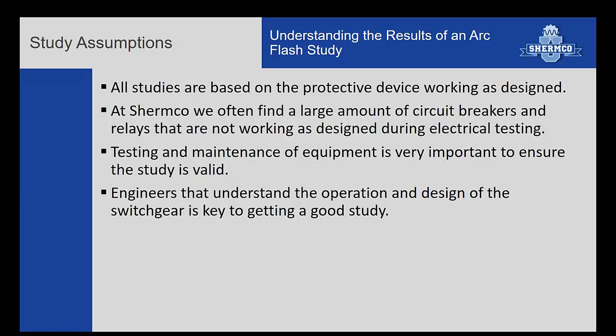So truly understanding what the sticker is talking about, not getting too close to the gear, and if you're further away, then maybe you can write a procedure to handle it. And then understanding assumptions, so that whenever we're making decisions, we understand what the engineer did. A lot of times the engineering firm that did your study can help you come up with, if I'm doing this task at a different distance, what would the arc flash be at that range?